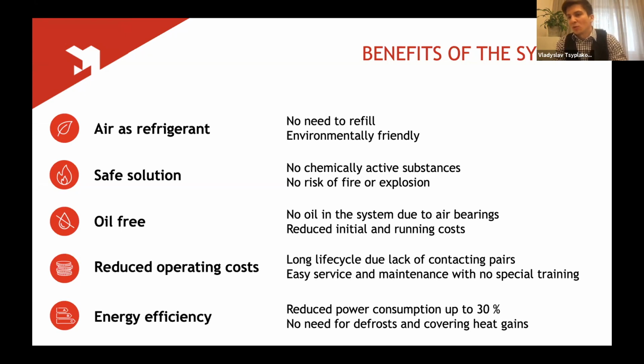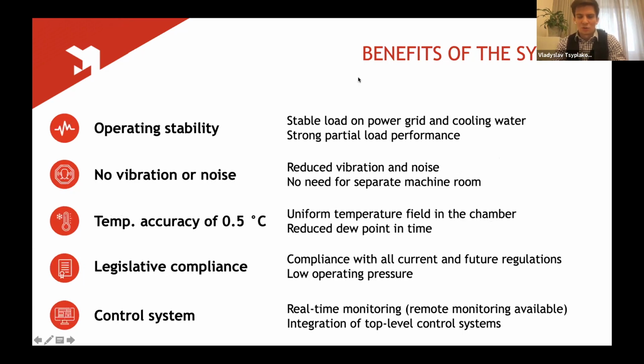So due to the lack of contacting pairs, we have the long life cycle of the equipment, and it's easy to service and maintain without any special training. And also with high energy efficiency, we have reduced energy consumption up to 30% by having a shared shaft between compressor and expander, because expander generates the energy, which is fed to the compressor. But also there's no need for defrost procedures of the chamber, and you can recover the heat from the refrigeration cycle.